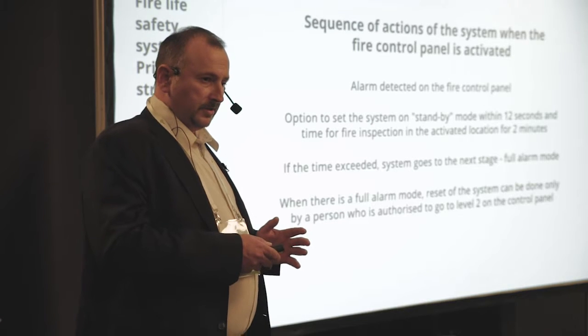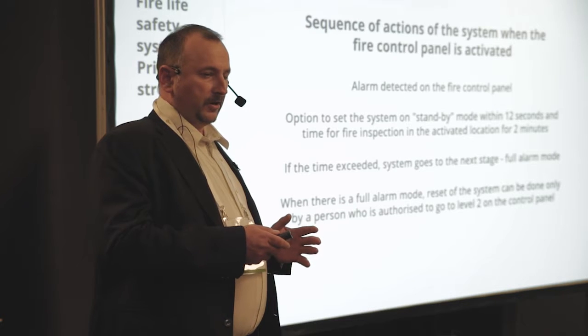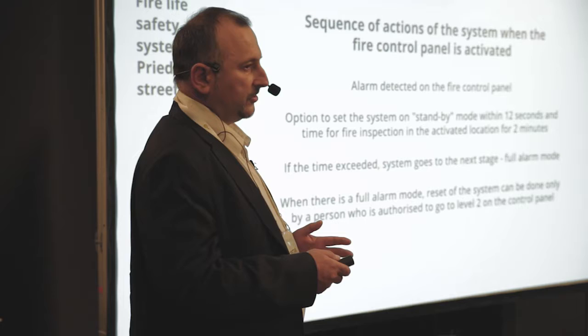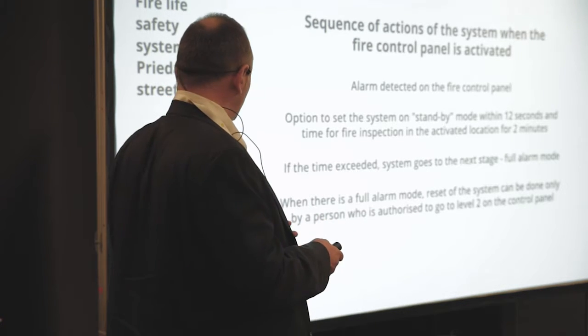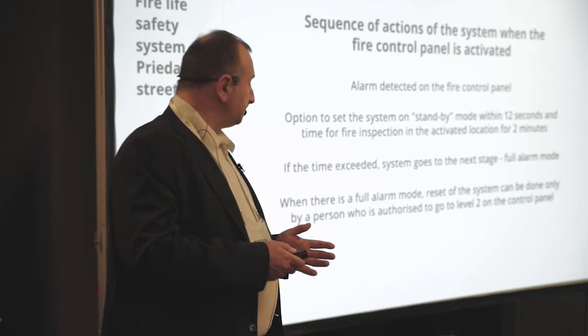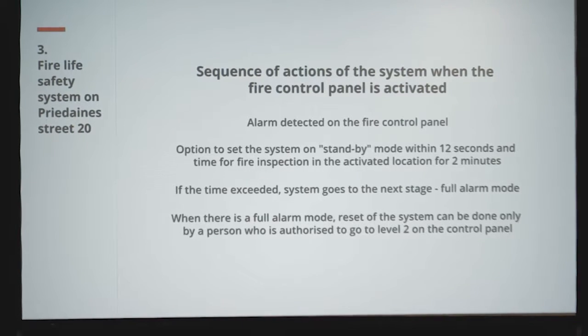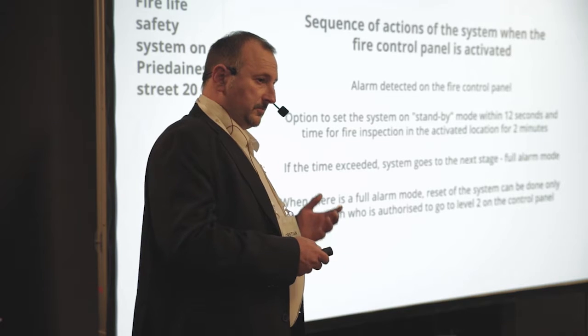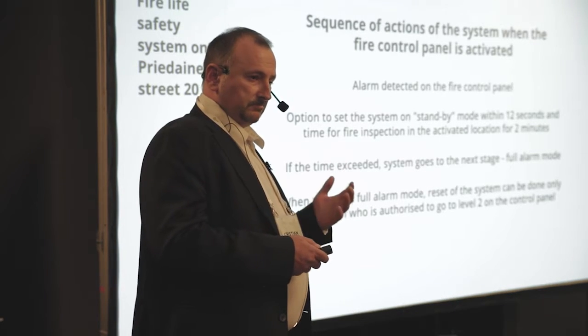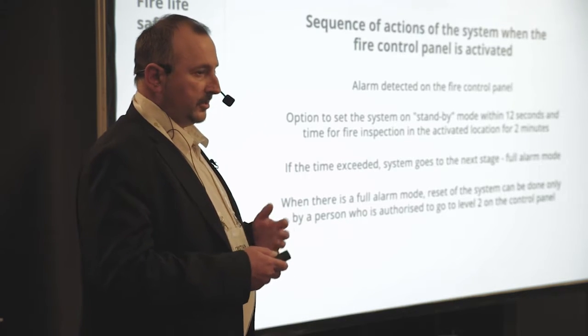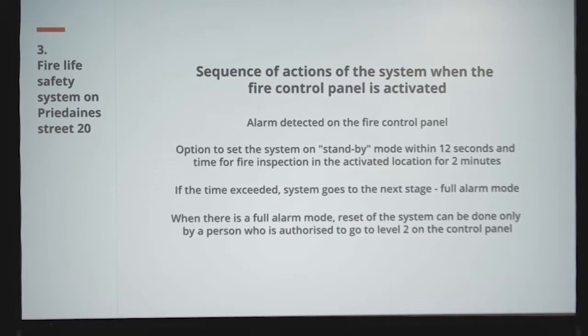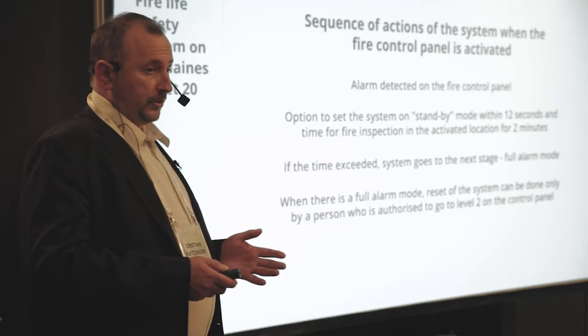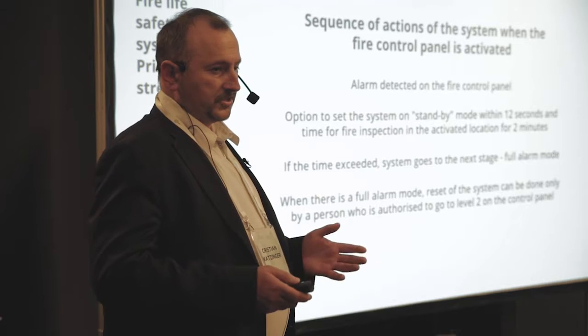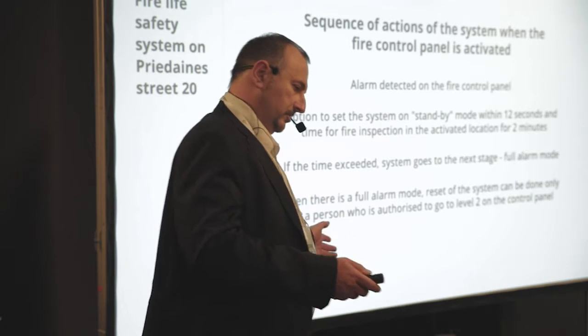At this point, a fire alarm can only be quit by a person who is authorized at the second level of the fire control panel to bring it back. But of course, if there would be a real problem, then the fire alarm would come again. If the fire alarm system is in full mode, then the automatic voice alarm system will go on to inform people who are in the building, and the smoke exhaustion system goes on. The normal ventilation system goes off to avoid turbulence, because in this case smoke could be brought down by ventilators, so they are switched off.